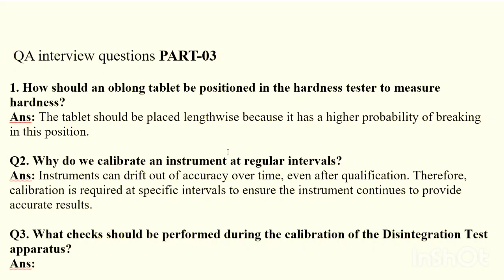The first question is: how should an oblong tablet be positioned in the hardness tester to measure the hardness? The tablet should be placed lengthwise. Oblong tablets need to be placed lengthwise in the hardness tester because it has a higher probability of breaking in this position.